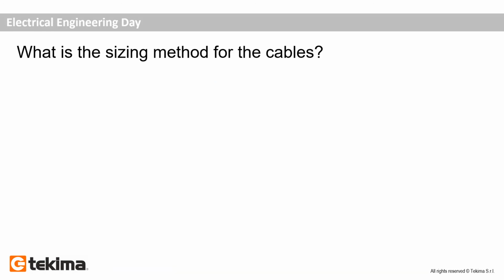Till now we have seen how to size the raceway, how to size the cable tray, and how to calculate the maximum operating ampacity of the cables contained. But what is the method to size the cables? In the previous example, the size of the cable was already defined. Let's see in the final example how to understand the size of the cables according to a specific standard.